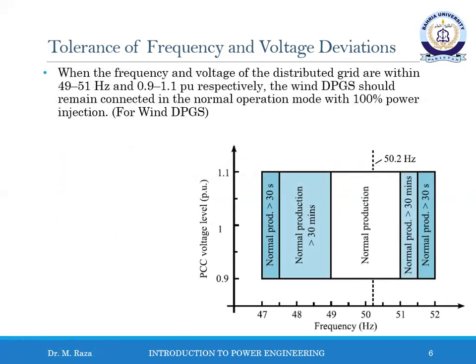Grid codes define different durations for which the distribution power generation system must operate normally depending on the network frequency variation. A typical frequency and voltage tolerance for a wind distribution power system is shown in this diagram. When the frequency and voltage of the distributed grid are within 49 to 51 Hz and the voltages are 0.9 to 1.1 per unit respectively, the wind distribution power generation system should remain connected in the normal operation mode with 100% power injection.